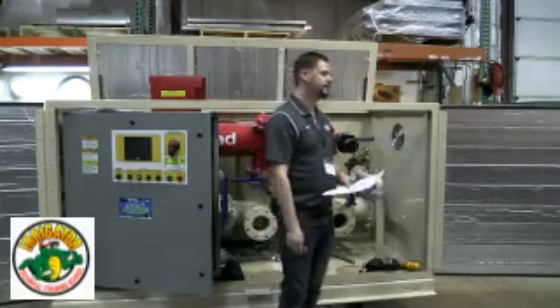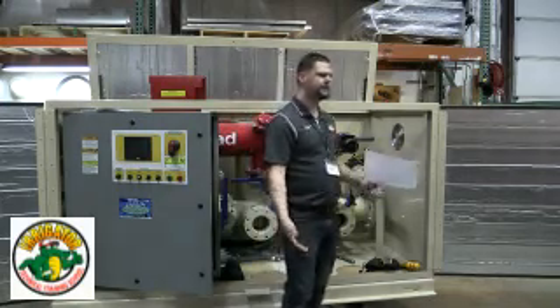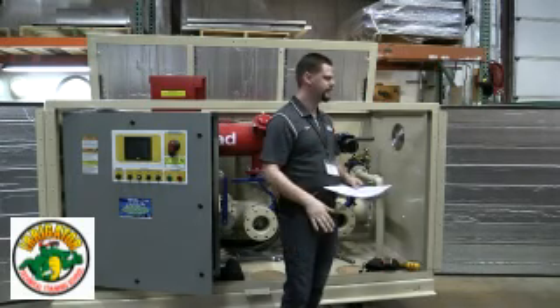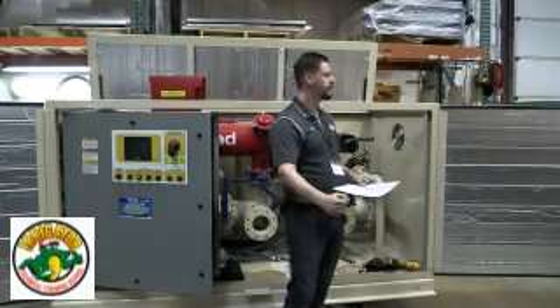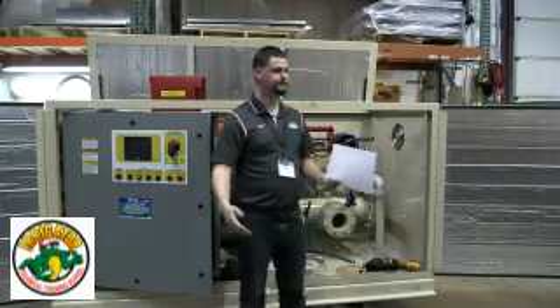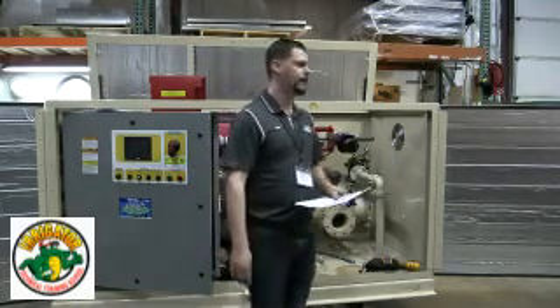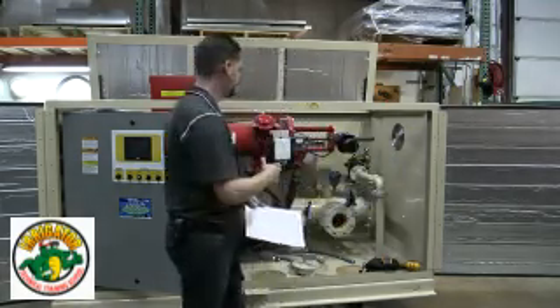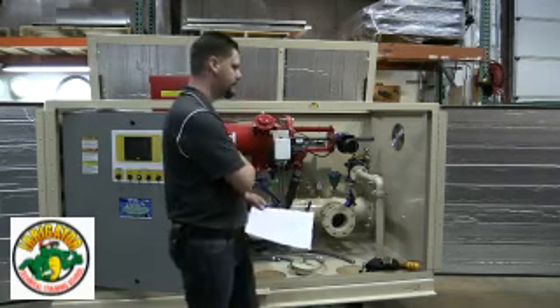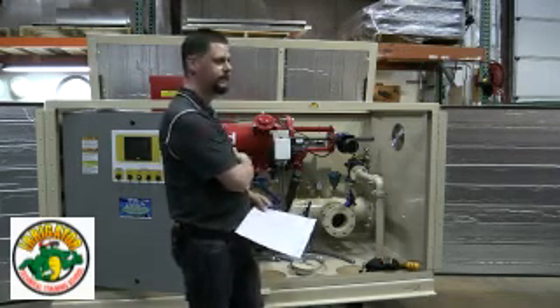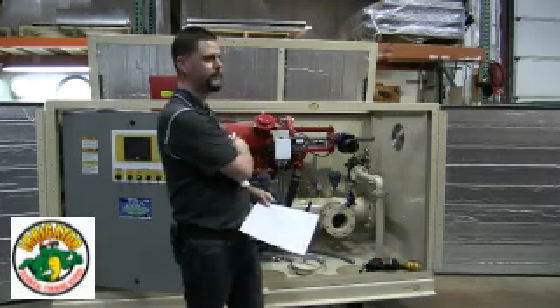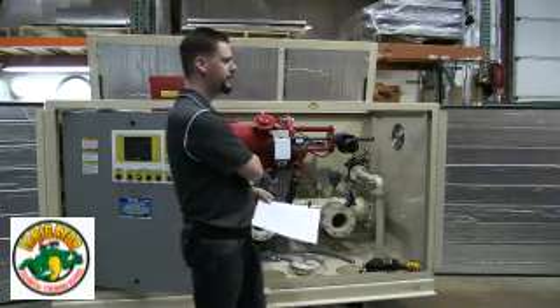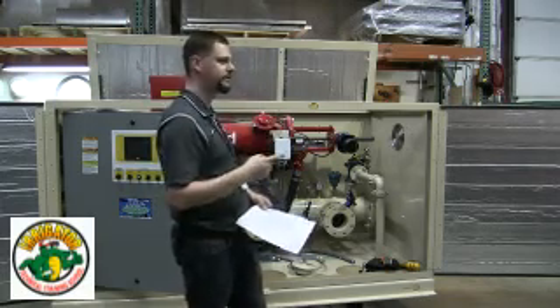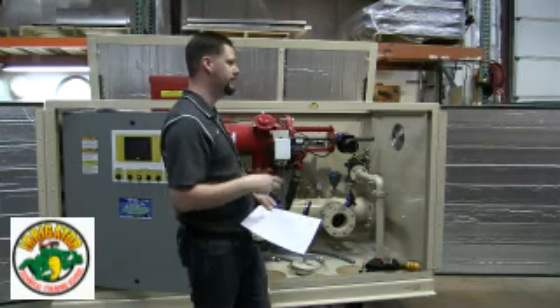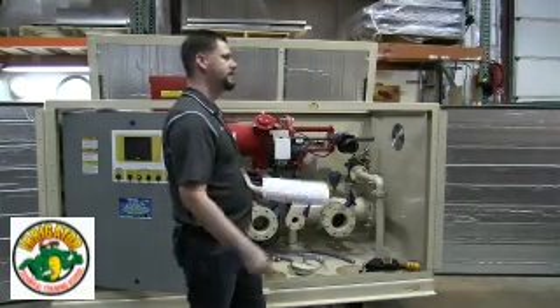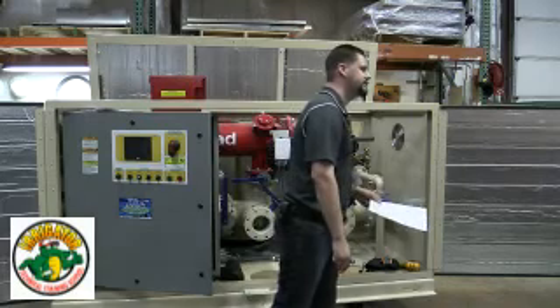everything, don't make an adjustment unless you are very aware of where the intake of that pump is in relation to the low water float. Now, only in auto, which is another reason you don't leave a pump in hand. I'm sure somebody said that. Don't leave a pump in hand and walk away, because it doesn't care about pressure. It doesn't care about water. It just knows it has to be on, and it says, how fast?